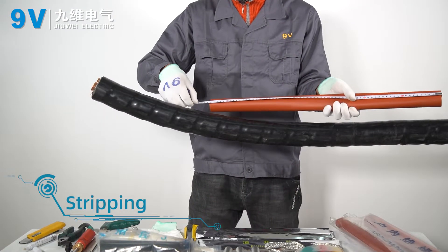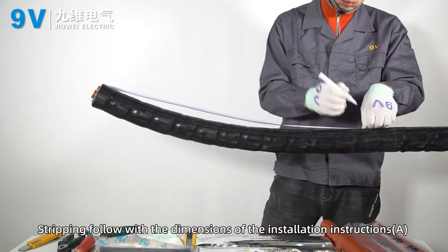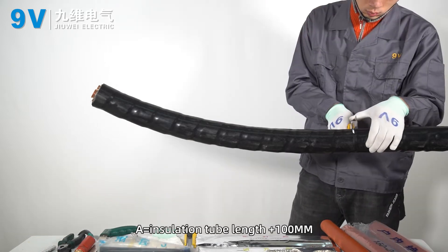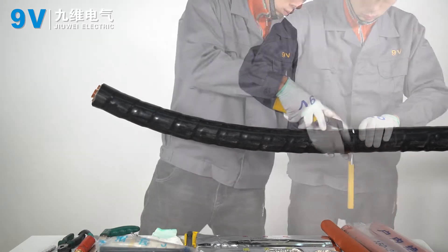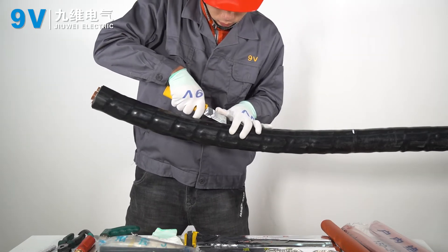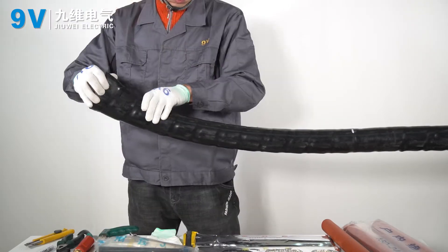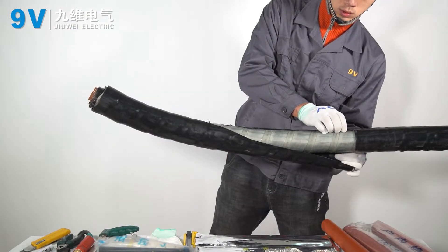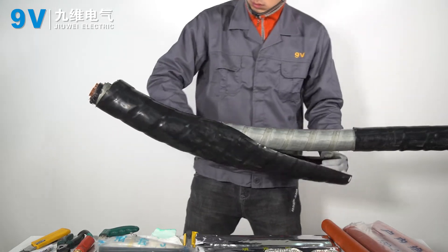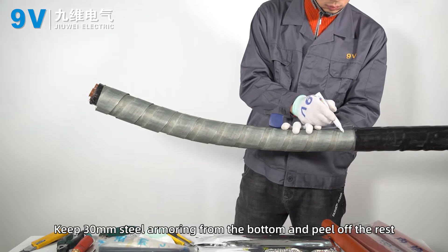Stripping. Strip following the dimensions of the installation instructions, where A equals insulation tube length plus 100 millimeters. Keep 30 millimeters of steel armoring from the bottom and peel off the rest.